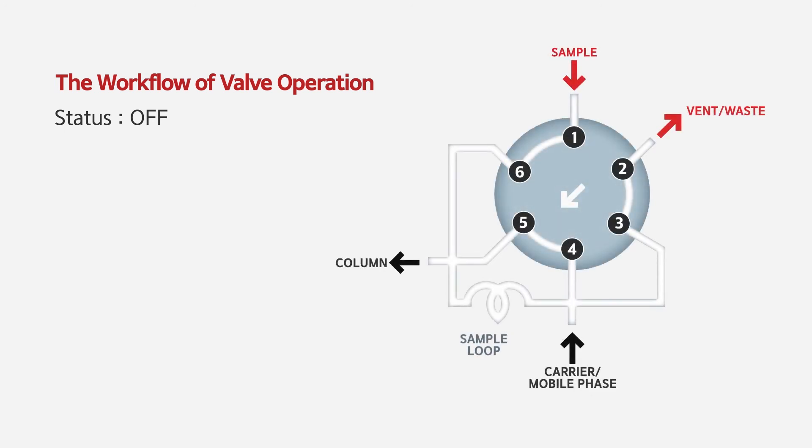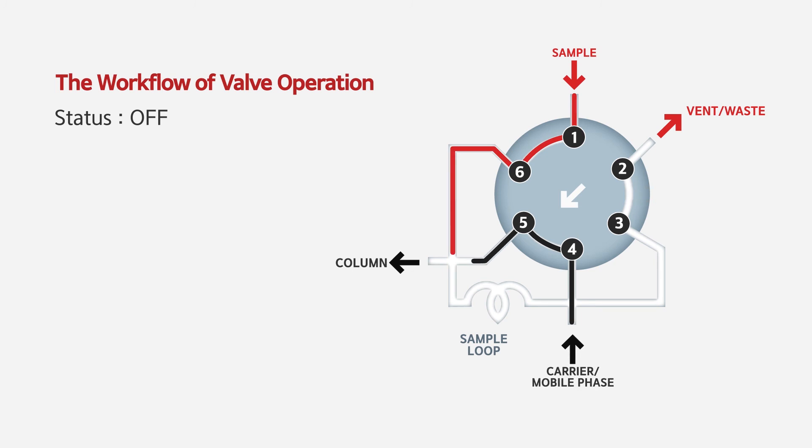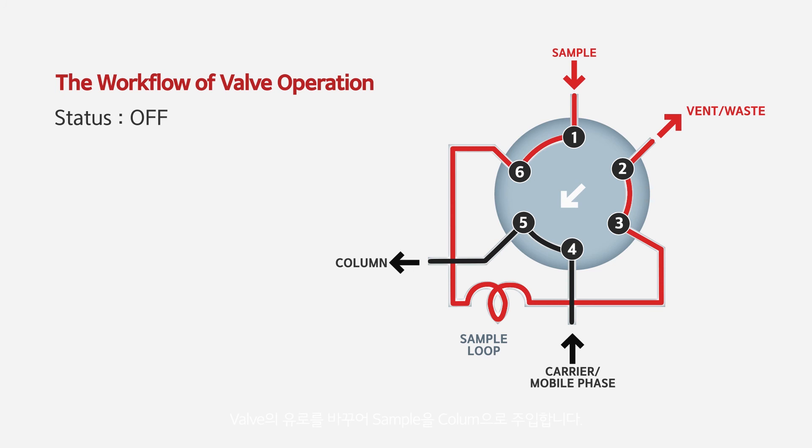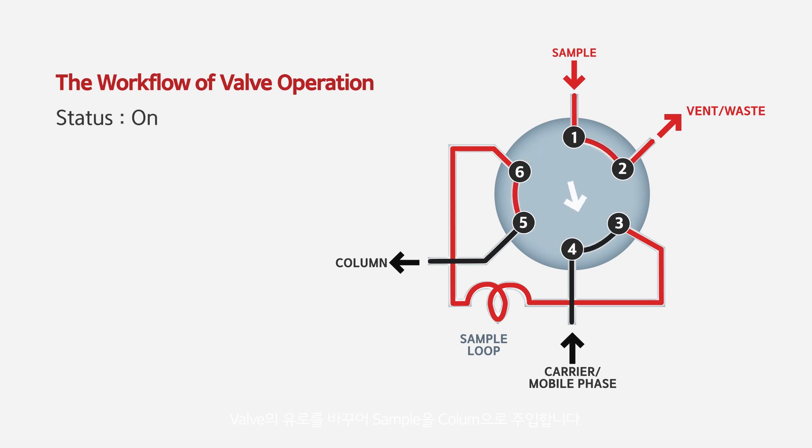As you see the valve diagrams, the sample loop is filled with the gas samples and the carrier gas flows to the column when the valve is off. When the valve is switched on, the carrier gas delivers the sample in the loop to the column.